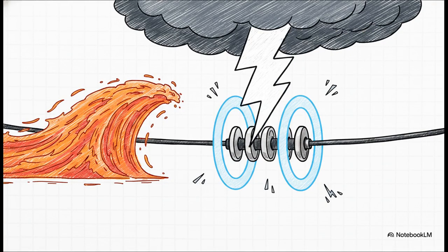And pollution isn't the only villain here. These insulators have to constantly absorb immense overvoltage shocks. Imagine a power line suddenly taking a direct hit from a lightning strike. The insulator has to absorb that millions-of-volts spike without shattering. But overvoltages don't just come from the sky. They can be generated internally by the grid itself. Sudden switching operations, like a massive circuit breaker opening or closing, can send a tidal wave of excess voltage down the line. Plus, phenomena like ferroresonance or the Ferranti effect on very long transmission lines can cause voltage to surge dramatically. The insulator just has to hold the line against all of these sudden electrical earthquakes.